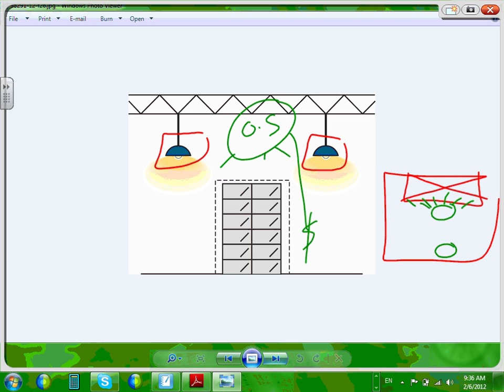So it should just be a standard on-off switch. A low voltage switch would work perfectly. You turn it on, or a high voltage switch like we did will work perfectly. Turn it on, and when you leave, you turn it off. With a low voltage system, if somebody in the mechanical room switched things off at night, they can sweep the whole system off. I don't know how that will qualify. I bet some inspector will not even qualify it, because in the middle of the night you're working, they sweep the whole light off, and you're dead. You almost have to have a manual override on it. The easiest way is to put it on a snap switch.